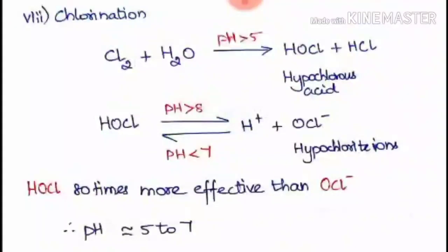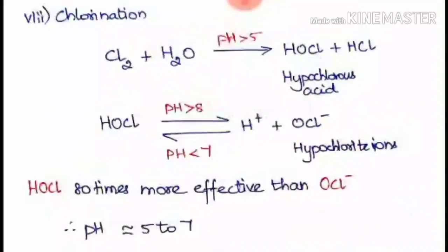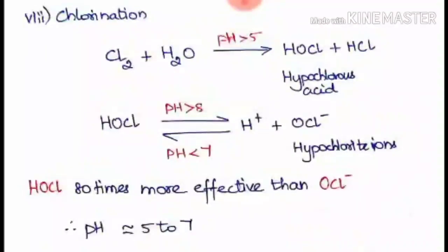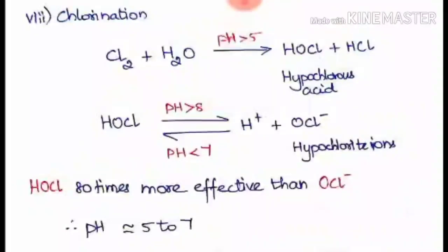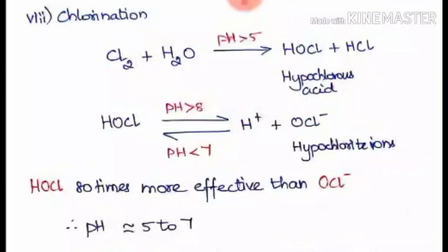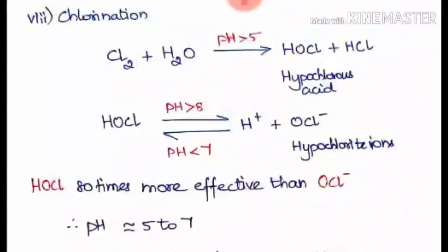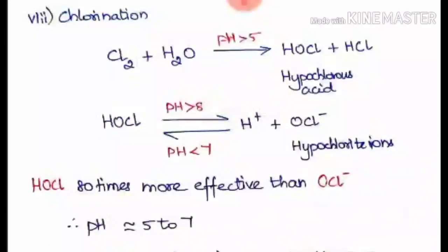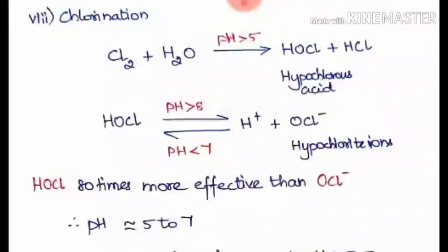The next is chlorination, the common basic method adopted all over the world. When chlorine reacts with water it gives HOCl, that is hypochlorous acid. This happens when the pH is above 5. This hypochlorous acid further dissociates into H⁺ and the hypochlorite ion. Both hypochlorous acid and hypochlorite ion are called free chlorine. HOCl is nearly 80 times more effective than the hypochlorite ion.